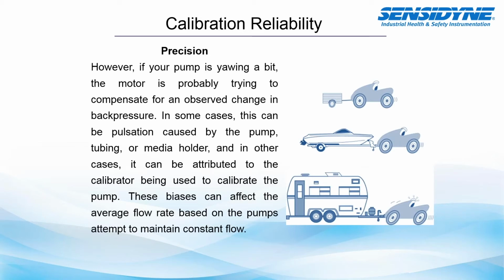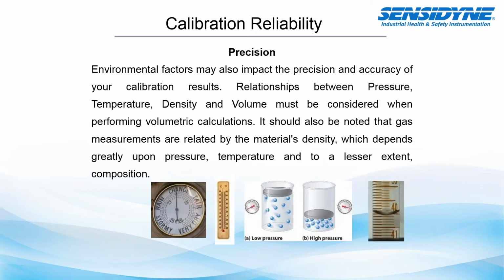Now, when thinking about precision, if your pump is yawing a bit, so you hear your pump starting to rev, the motor is probably trying to compensate for an observed change in the back pressure. So in some cases, this can be pulsation caused by the pump itself, caused by tubing or the media holder that it's in. And in other cases, it can be attributed to the calibrator being used to calibrate the pump. Now, these are biases that can affect the average flow rate based on the pump's attempt to maintain constant flow. Additionally, environmental factors may also impact the precision and accuracy of your calibration.